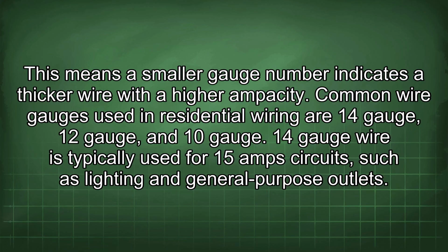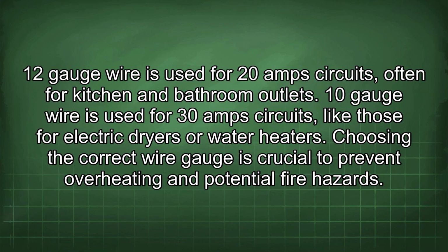14 gauge wire is typically used for 15 amp circuits, such as lighting and general purpose outlets. 12 gauge wire is used for 20 amp circuits, often for kitchen and bathroom outlets. 10 gauge wire is used for 30 amp circuits, like those for electric dryers or water heaters. Choosing the correct wire gauge is crucial to prevent overheating and potential fire hazards.